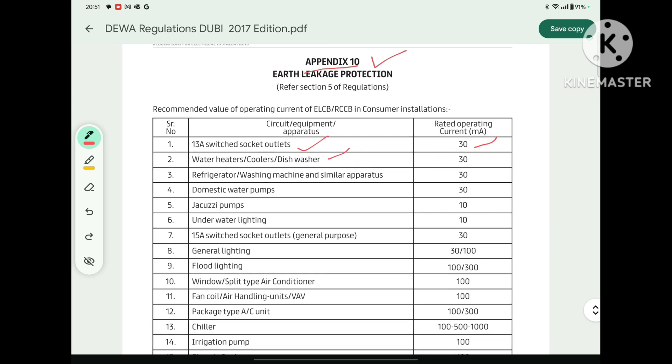As per Appendix 10, DEWA says that for a 13 Ampere switch socket outlet, the ELCB sensitivity rating should be 30 mA. In a home we have single-phase 13 Ampere switch socket outlets, and they will be controlled by one ELCB, so that ELCB rating must be 30 mA. In the same way, for water heater, cooler, and dishwasher, the sensitivity rating is 30 mA. For refrigerator, washing machine, and similar appliances, it must be 30 mA. For domestic water pump, the sensitivity rating is also 30 mA.